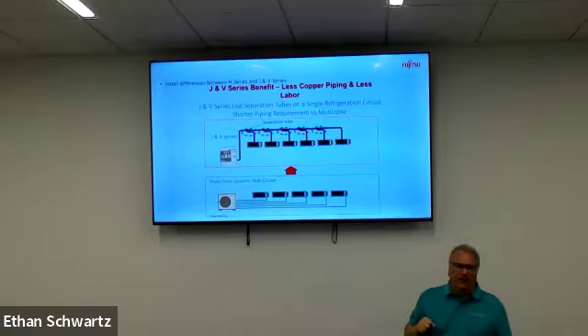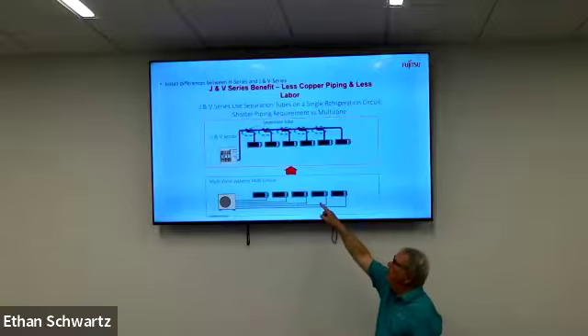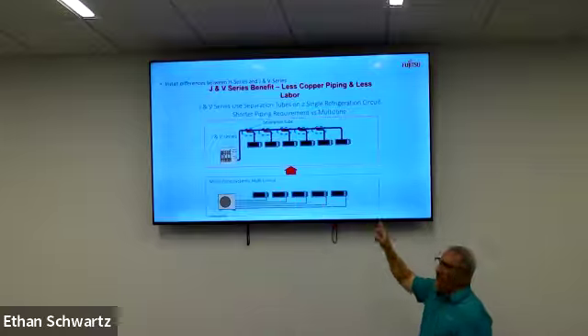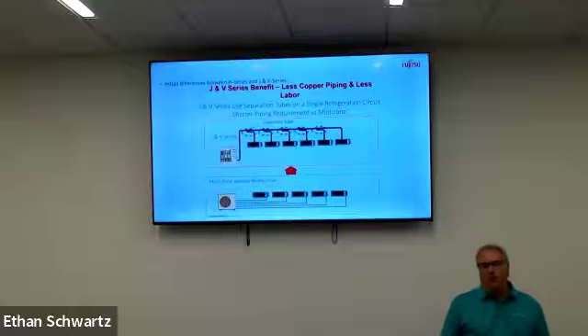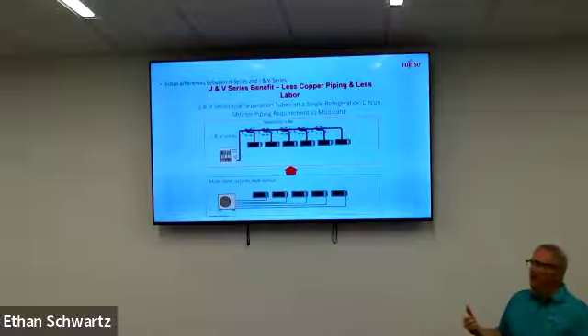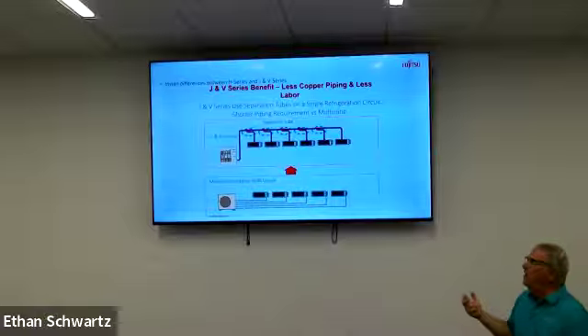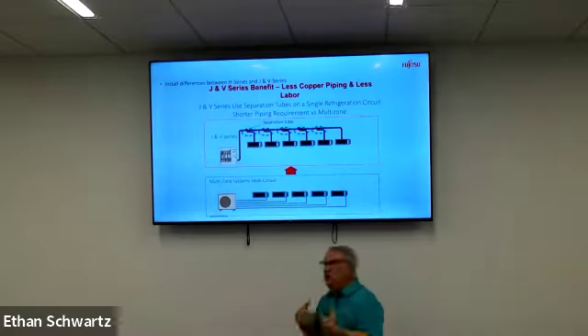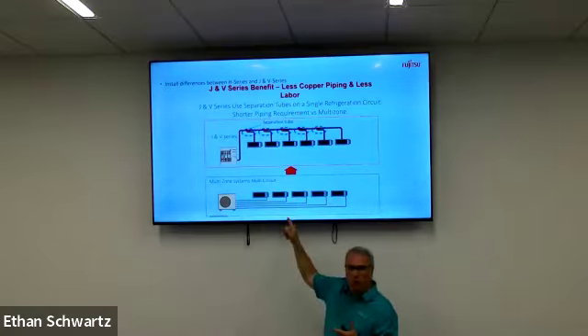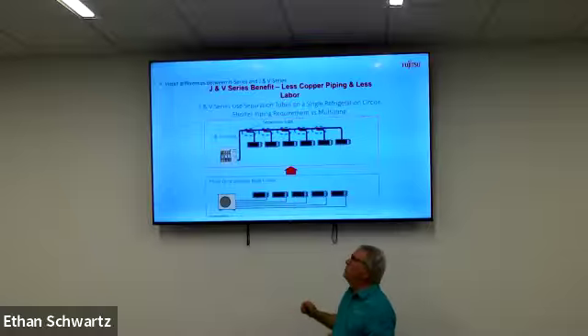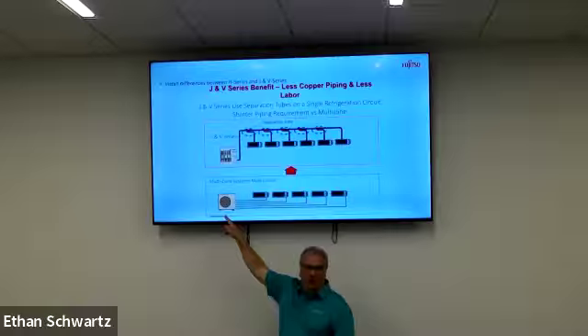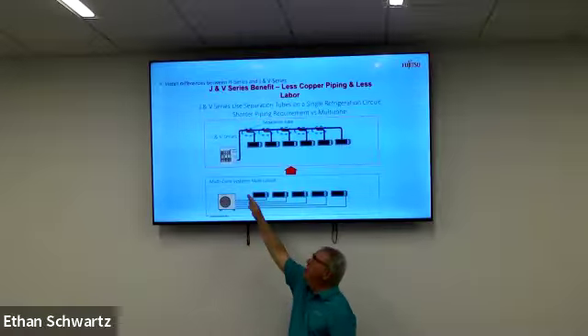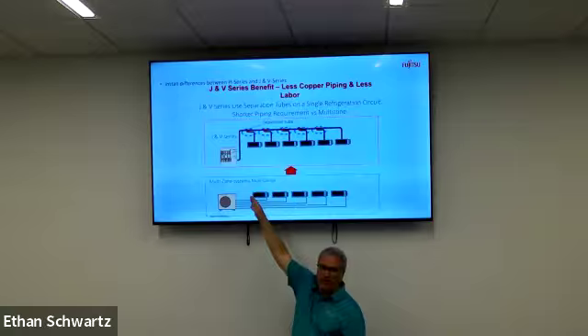J series is different because it's still single phase, but you're going to have a 2-pole circuit breaker for the outdoor unit, needing 2 circuit breaker spaces in the panel, and then a 2-pole circuit breaker to feed all of the indoor units. There's a couple models that need to be set up on their own, but none of them really draw that much that you couldn't put them on one 2-pole circuit breaker. So when the contractor is looking at switching from one to the other, and he's working up his quote, 2 breaker spaces required in the panel here, 4 with the J series. Does that make sense?